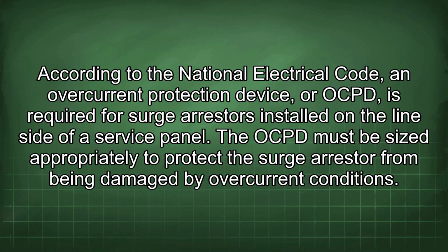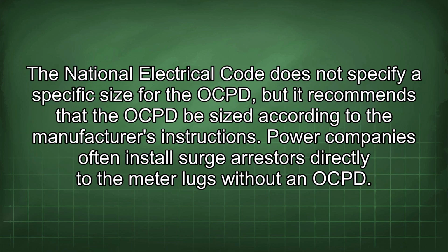According to the National Electrical Code, an overcurrent protection device, or OCPD, is required for surge arrestors installed on the line side of a service panel. The OCPD must be sized appropriately to protect the surge arrestor from being damaged by overcurrent conditions. The National Electrical Code does not specify a specific size for the OCPD, but it recommends that the OCPD be sized according to the manufacturer's instructions.